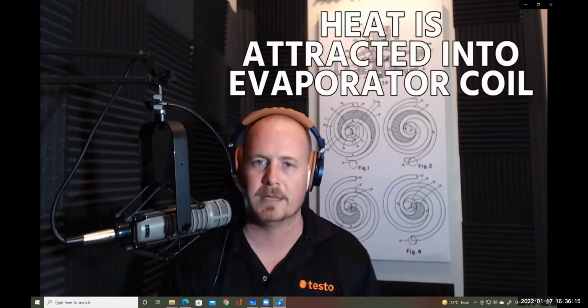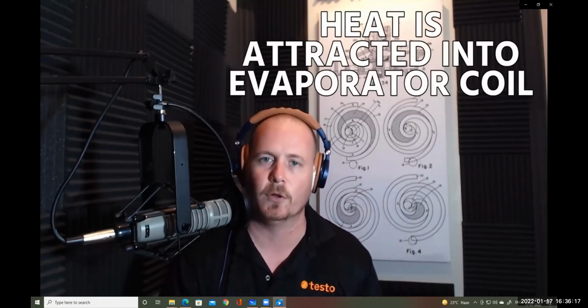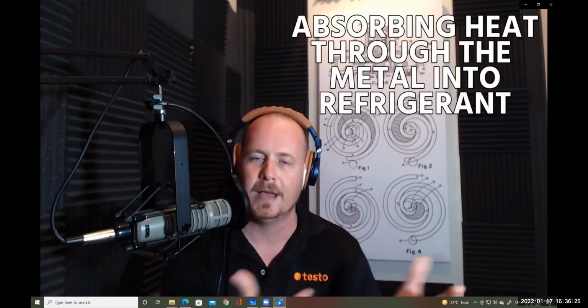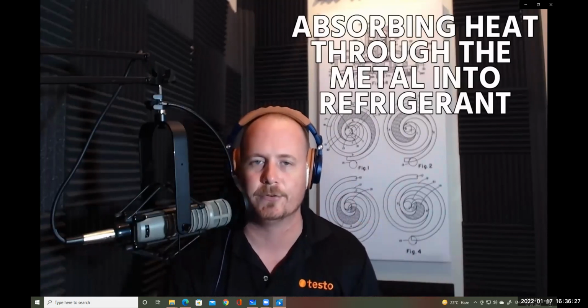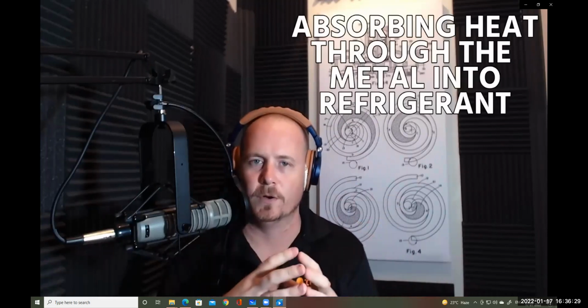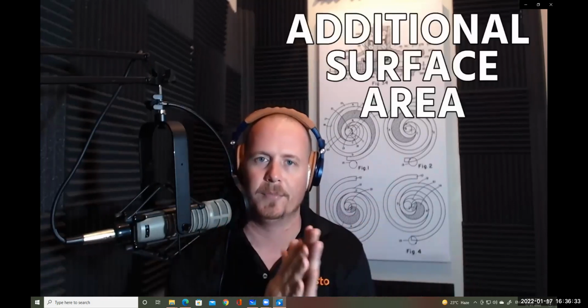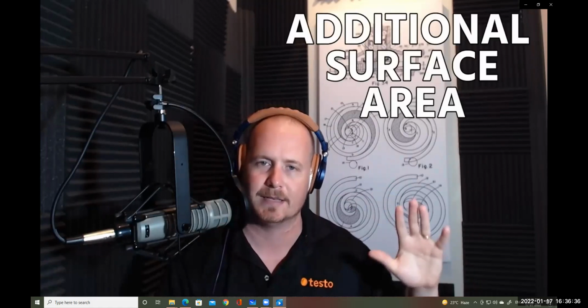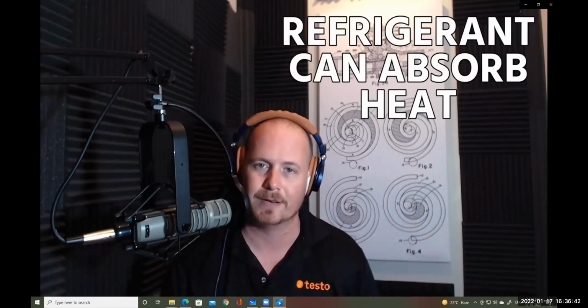And for most of the typical basic systems we're working on, we're just flowing air over the evaporator coil, over those fins, and as it passes across that metal and the refrigerant moves through, it's absorbing heat through the metal into the refrigerant. The fins on those coils act as additional surface area to give a bit more contact time as the air passes over the metal, so that the refrigerant inside that evaporator coil can absorb heat.